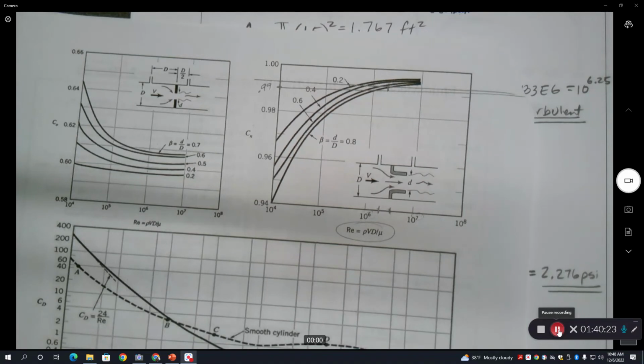But you're usually probably pretty okay if you're on the discharge side of something, because the pressures are high. It's really the cavitation thing becomes a real big issue when you're on the suction side of a pump, because you might already be below atmospheric pressure. Okay. And some pumps can't even, this is more information than you want, but a lot of pumps are arranged in such a way that you need to prime them first before they'll actually suck, right?